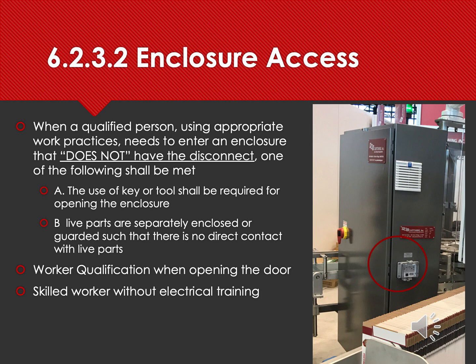B states live parts are separately enclosed and guarded such that there is no contact. Okay, so if the live parts are guarded against the control components, somebody is opening the panel, so they can do it. Okay. The next question here is, is every panel designed to have an isolated power compartment? So these are the things that one needs to consider while designing the industrial control panels.